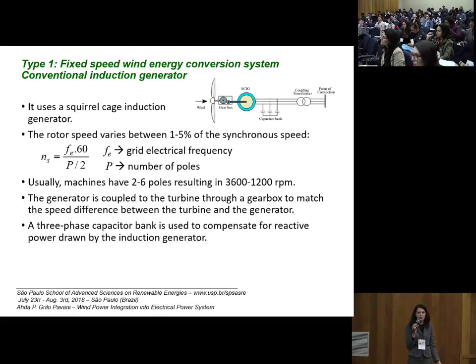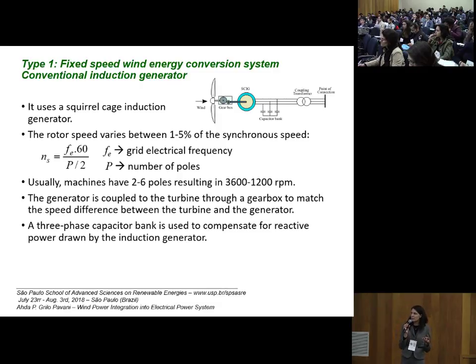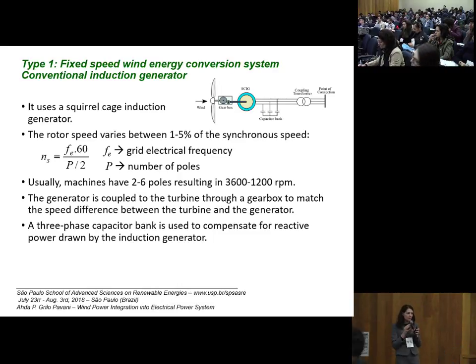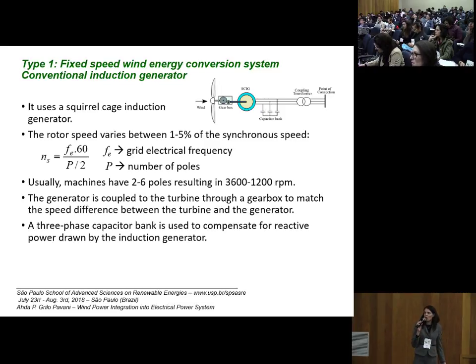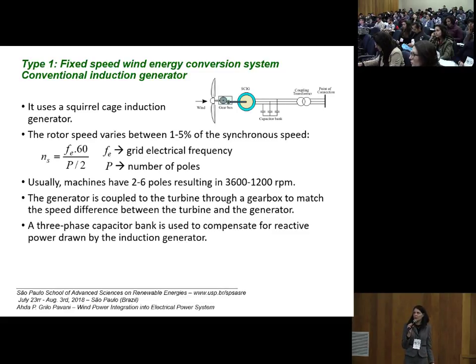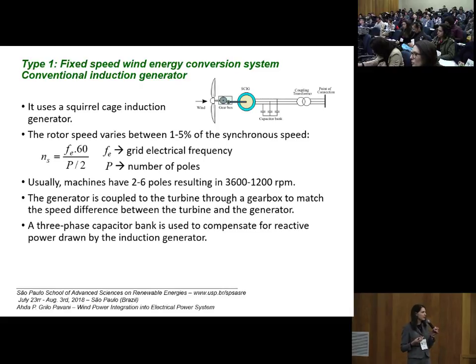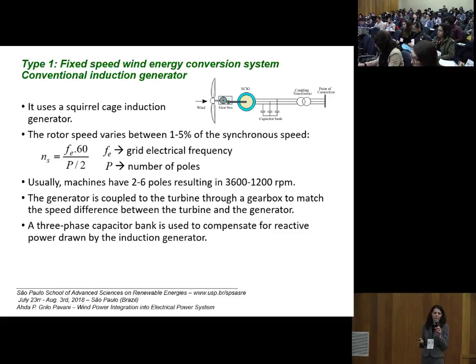The synchronous speed depends on the number of poles and the electrical frequency of the machine, as shown in this equation. Squirrel cage induction machines typically have 2 to 6 poles, resulting in a rotary speed of 3600 to 1200 RPM. The generator is coupled to the turbine through a gearbox to match the speed difference. Because the induction generator consumes reactive power, a capacitor bank is connected at the output to improve the power factor.